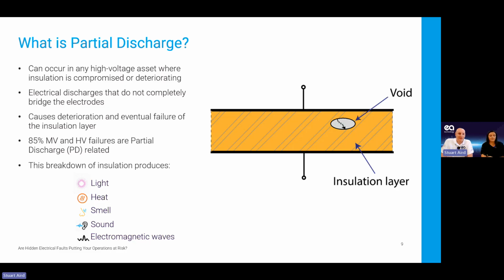Okay. So today we're talking about hidden problems within our medium voltage and high voltage assets. And one of the best indicators and one of the main ways that these assets can fail is through failure of the insulation material that's keeping the electricity safe inside the switchgear or electrical transformers and things like that. So it will occur in any high voltage asset where insulation is being compromised or deteriorating. The electrical discharge is a partial breakdown, so it gives us an indication that it's partially starting to break down, and hopefully if we can pick it up before it finally fails, then we can prevent these failures.